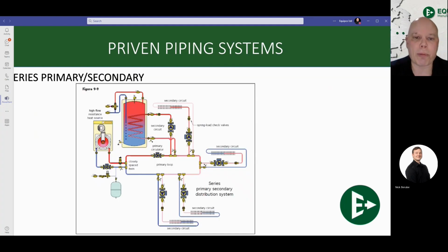Here's another example of your primary secondary series piping. We also have the boiler on its own circuit off of your primary loop. This is what's going to be known as your primary secondary injection, where the boiler is going to be injecting heat into that primary loop. It's again a tremendous amount of pipe. We don't do this a whole lot anymore unless we have to, and again, it requires pretty advanced controls to control all the temperatures going out into the system. But this is your primary secondary system, just with an injection of the boiler.